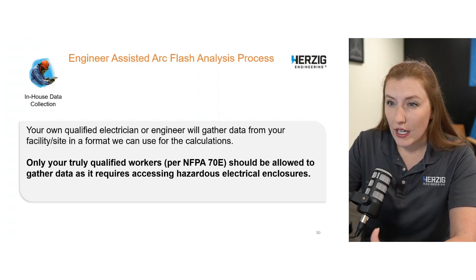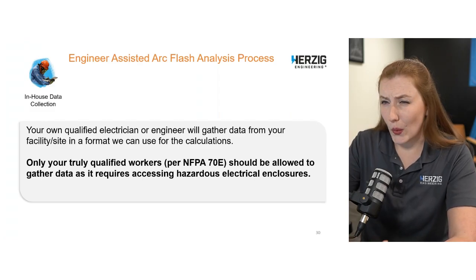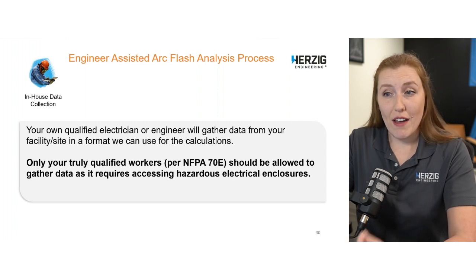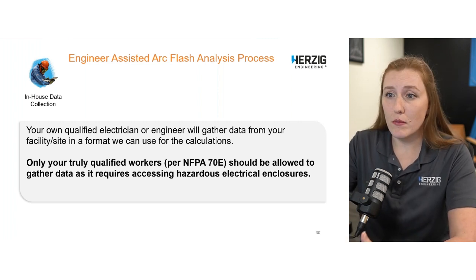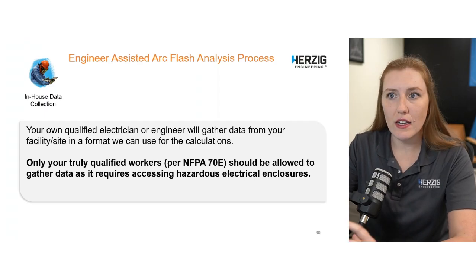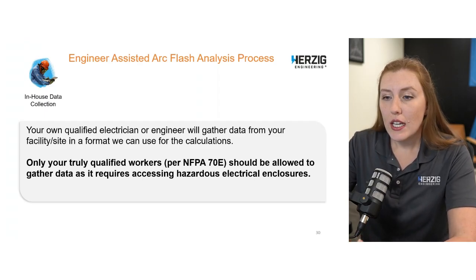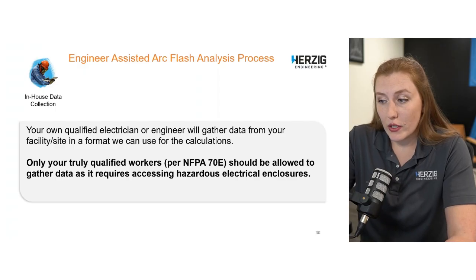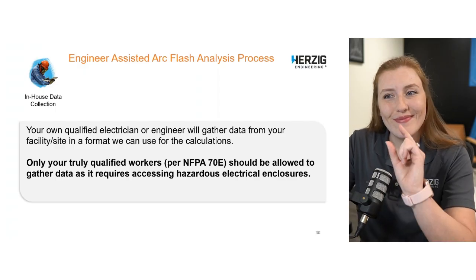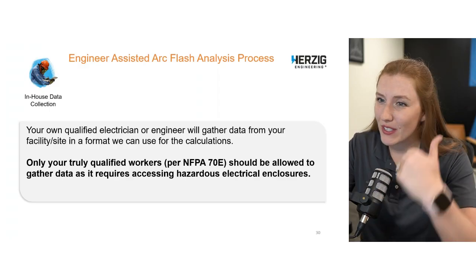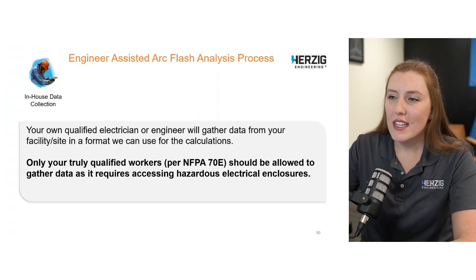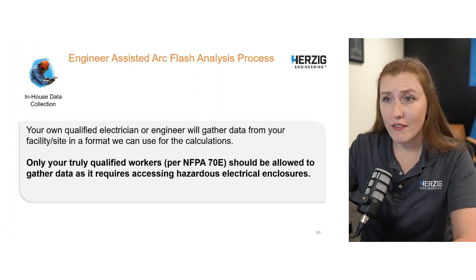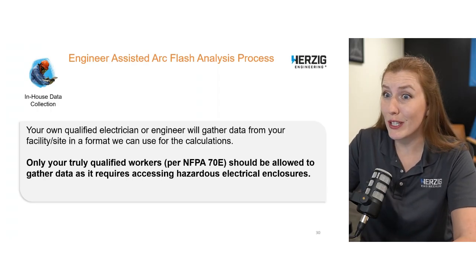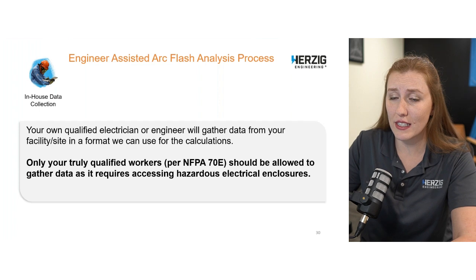You're looking at it, you're writing it all down. If you have one-line diagrams and as-built drawings and things like that, that's great. Usually it doesn't include everything we need though, so we still have some gaps where they need to write some stuff down and take some pictures with the covers off. If you do decide to do it during a shutdown week and everything's been verified off, you still have to have a qualified person do that step. You still have to have them verify that it's off. So again, don't just throw anybody on this task because they have time. It needs to be someone who's truly qualified and knows a lot of detail about your electrical distribution system. Probably your highest qualified person is going to have to be dedicated to this.